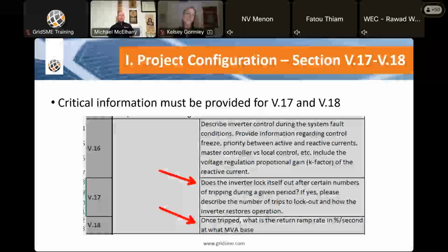So we're now getting into a couple of them. Does the inverter lock itself out after a certain number of trips during a given time period? There's really no good way to answer this question within the Attachment A workbook. What we've been getting back from CAISO, and what we have confirmed with them, is that they are looking for all of the reasons that the inverter could trip. It might be a sensor failure, it might be loss of voltage, there's all sorts of things. And we typically will work with them to include in the inverter settings report the list, and whether it can be automatically recovered or requires manual intervention.